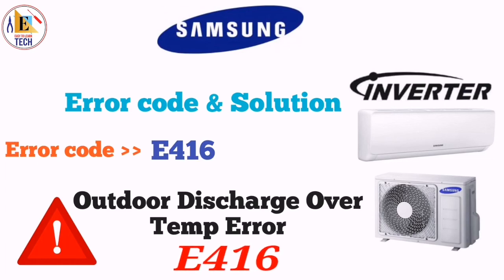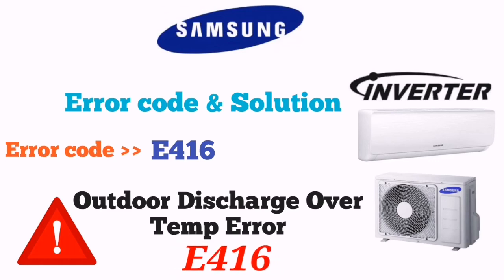When we restart our unit after 30 minutes or 1 hour, if it shows the error again, that means the condition for our air conditioner to operate is poor. Again, we have to wait until the discharge temperature decreases and restart our unit. If it again shows the same error, then download the EPROM data, and if it still shows the same error, change the outdoor PCB. If it is still not working after changing the outdoor PCB, then you have to change the compressor and your unit will be in working condition.